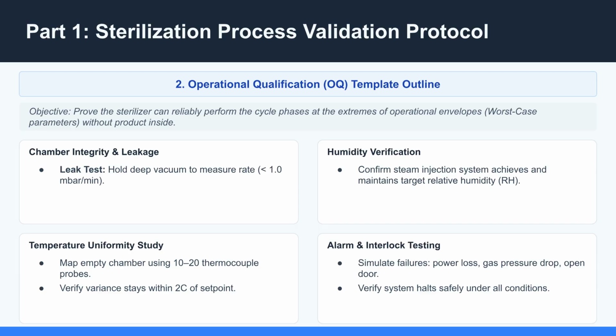Testing includes chamber leak tests, humidity verification, temperature uniformity, and alarm and interlock function checks.